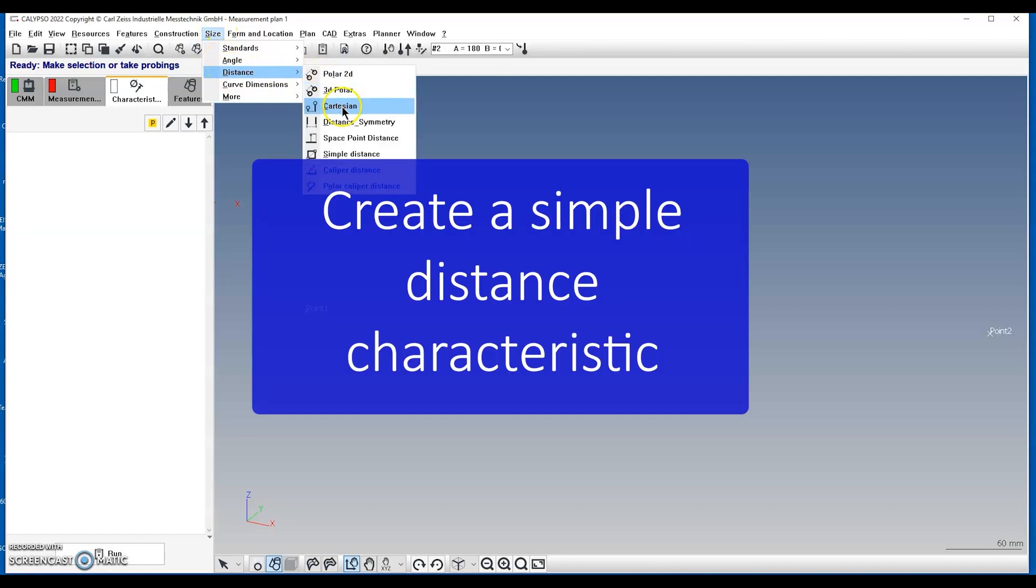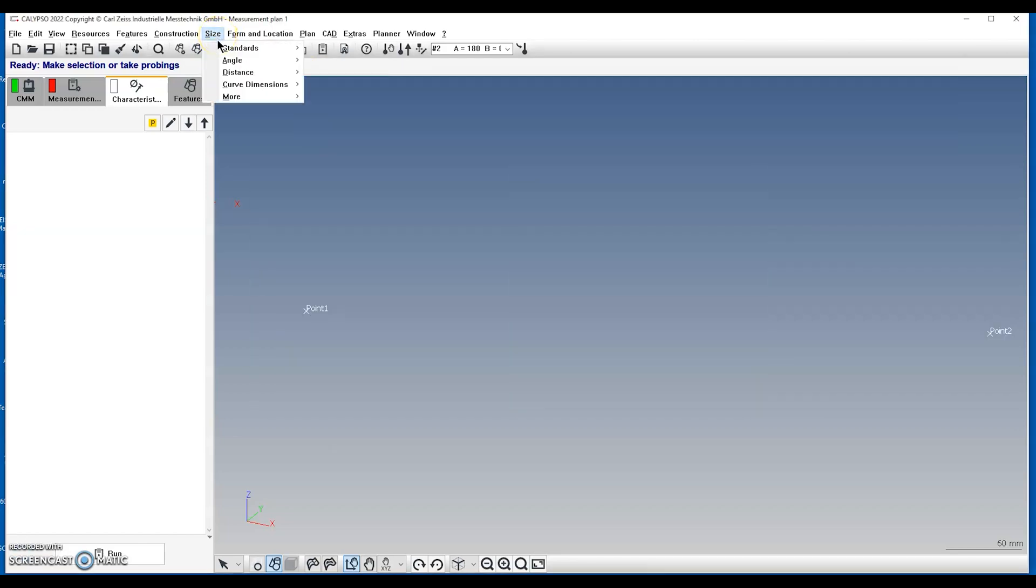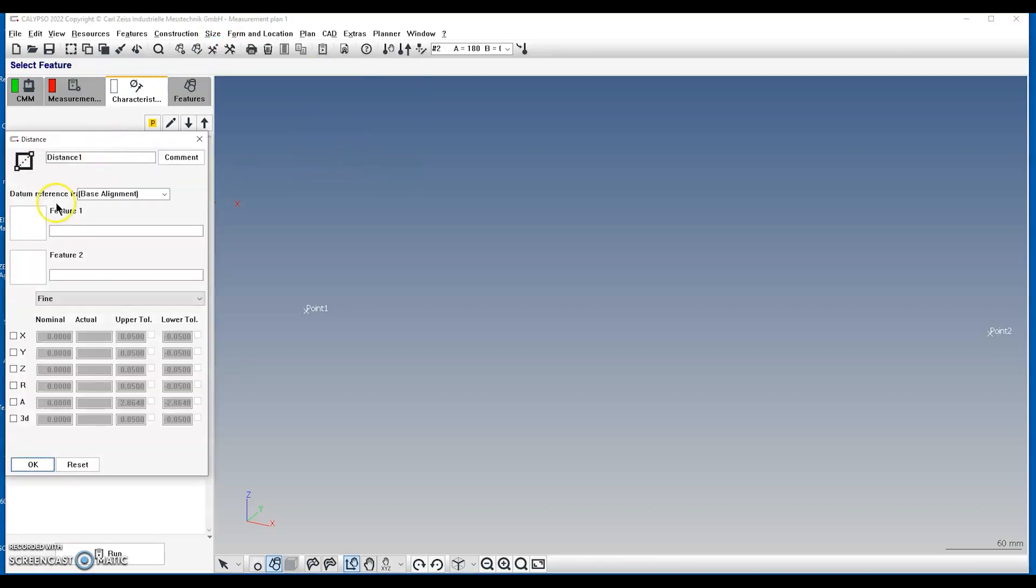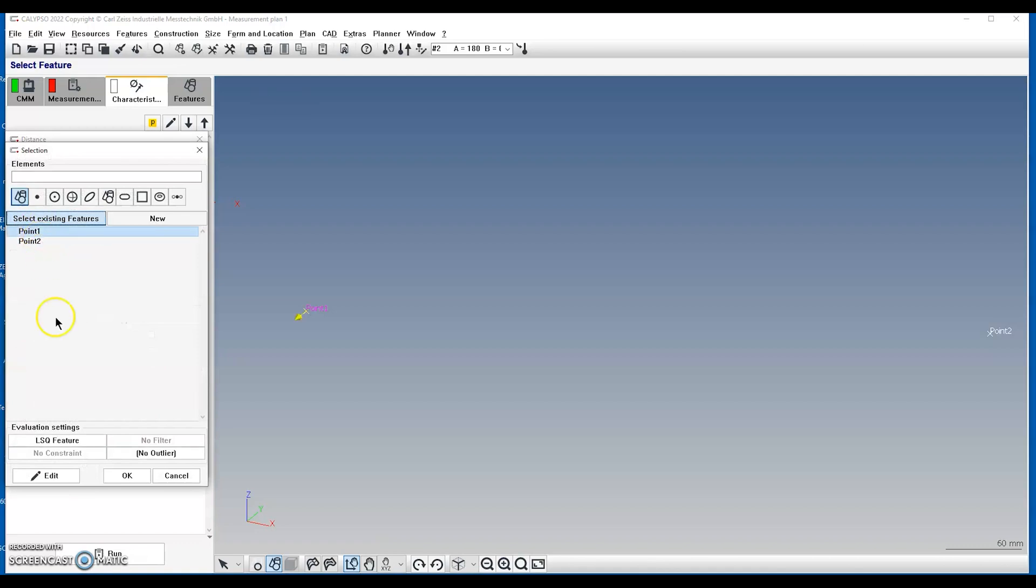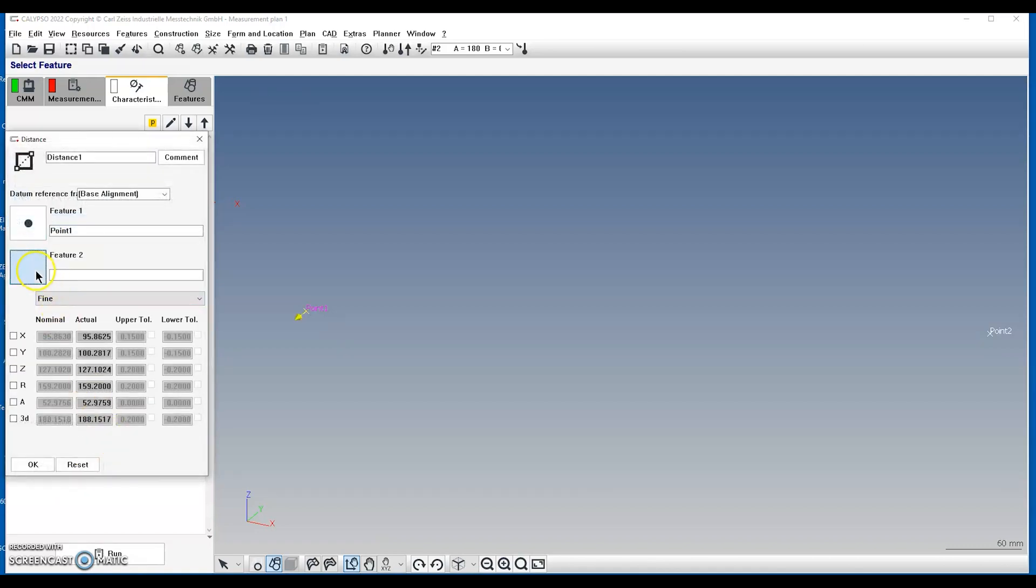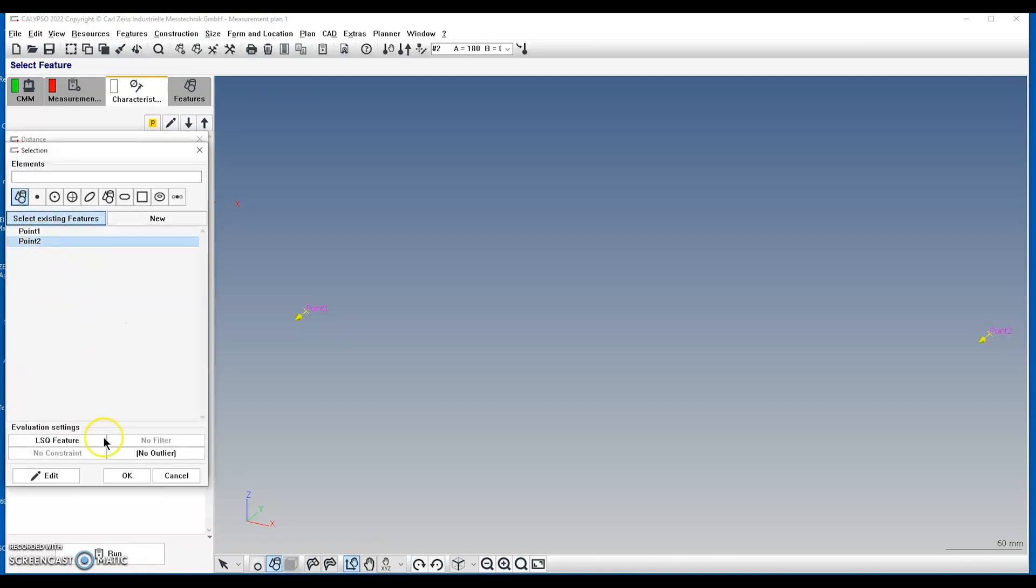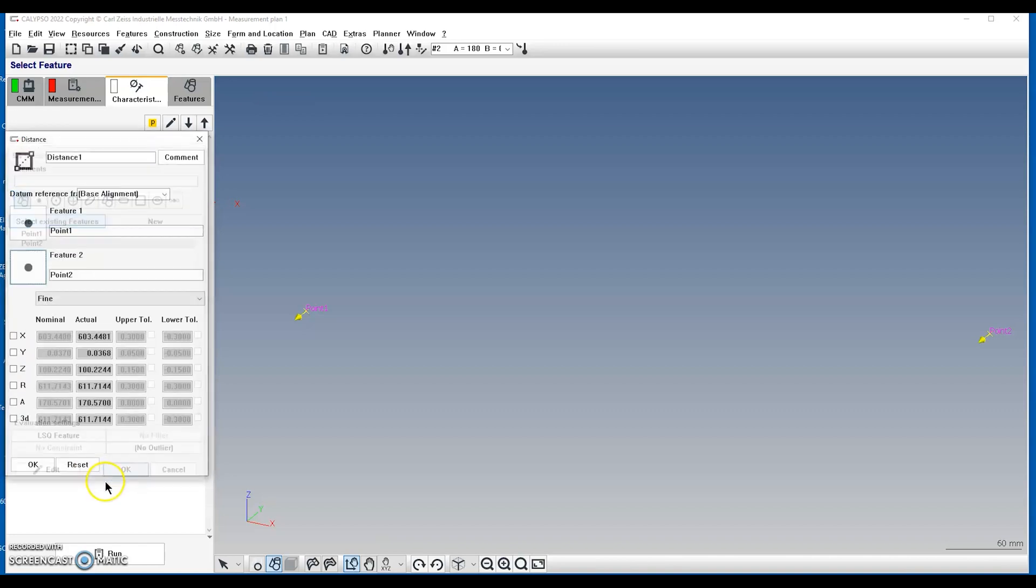Create a simple distance characteristic between the two points you just measured. Make sure the distance in the y direction is 0.04 or smaller. If it's greater, loosen your hardware, adjust the tool rack, re-tighten the hardware, and repeat this process of probing a point on the left and right side and creating that simple distance in the y direction.